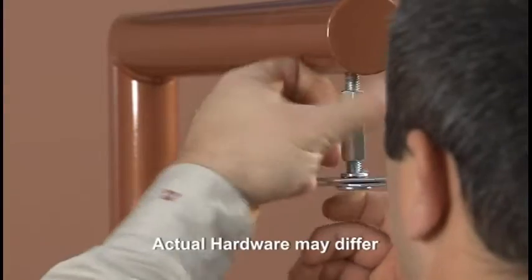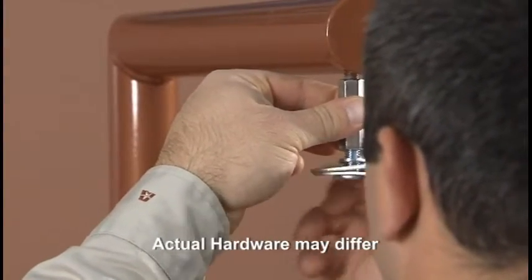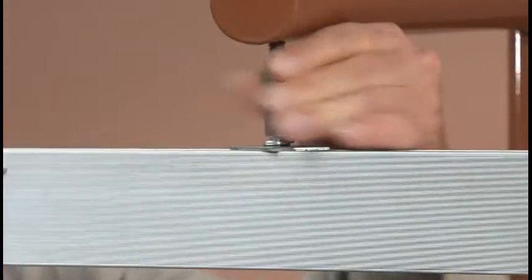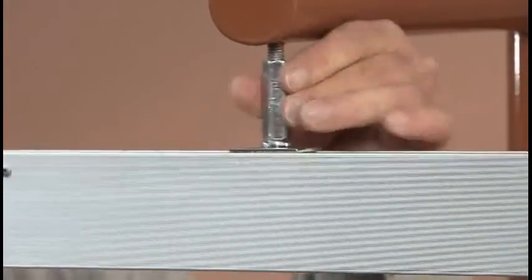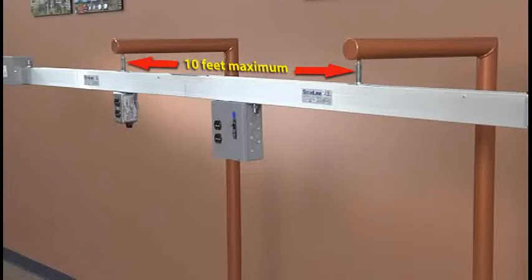Next, locate your hangers. There are multiple ways to hang the busway, but threaded rod hangers are most commonly used. Hangers can be inserted anywhere along the busway and have a maximum support spacing of 10 feet. Please note that hanging hardware may differ.